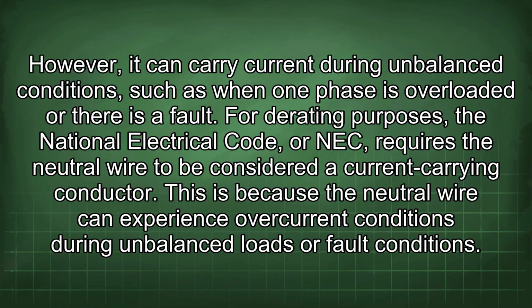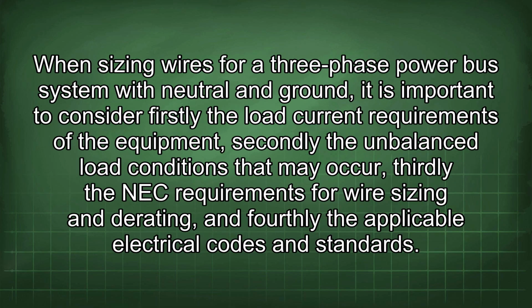For derating purposes, the National Electrical Code, or NEC, requires a neutral wire to be considered a current-carrying conductor. This is because the neutral wire can experience overcurrent conditions during unbalanced loads or fault conditions. When sizing wires for a three-phase power bus system with neutral and ground, it is important to consider firstly the load current requirements of the equipment, secondly the unbalanced load conditions that may occur, thirdly the NEC requirements for wire sizing and derating, and fourthly the applicable electrical codes and standards.